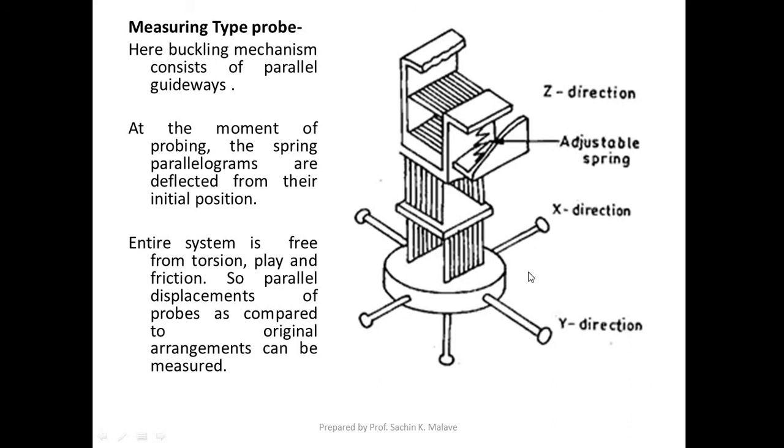Whenever a probe in a particular direction touches the component, the buckling mechanism comes into the picture. As you can see, there are 3 parallel guideways, one for each direction: one guideway for x direction, another for y direction, and a third for z direction.